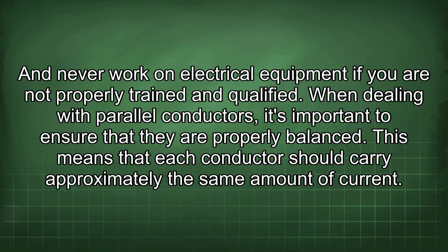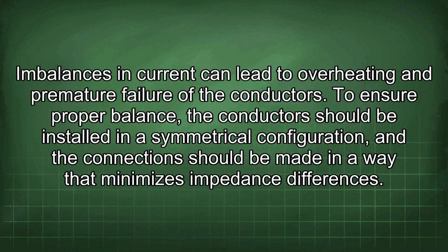When dealing with parallel conductors, it's important to ensure that they are properly balanced. This means that each conductor should carry approximately the same amount of current. Imbalances in current can lead to overheating and premature failure of the conductors. To ensure proper balance, the conductors should be installed in a symmetrical configuration, and the connections should be made in a way that minimizes impedance differences.